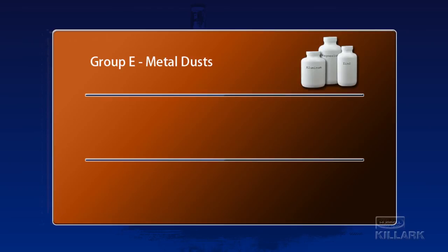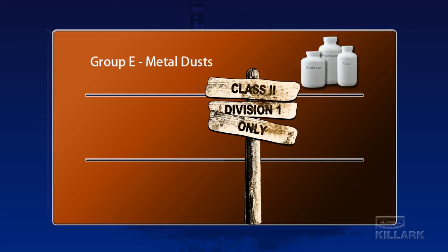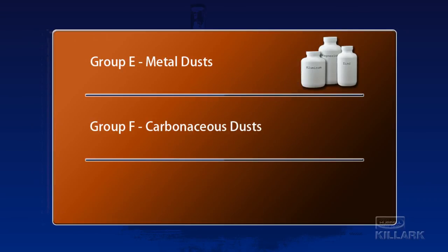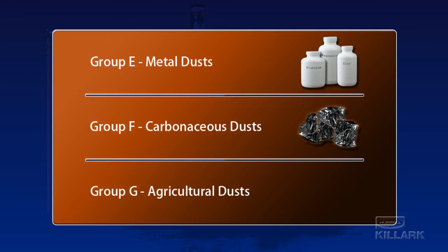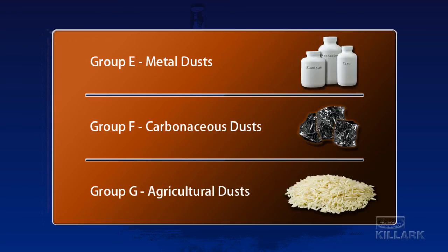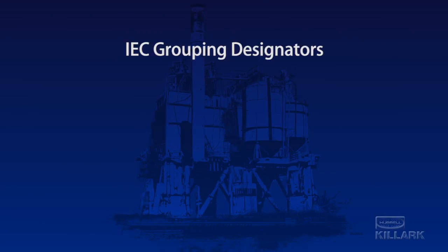The characteristics of various dusts also require groupings in the assessment of their potential behavior. In the division system, Group E contains metal dusts. Because of the conductivity of metallic dust, there is a special assessment rule that they must always be designated Division 1 under the North American approach. Group F includes solid fossil fuels and or similar carbonaceous material, such as coal and coke dusts. Group G covers grain and other agricultural dusts that are created during the processing and handling of products like wheat, rice, and corn. The IEC also uses groups based on material characteristics.